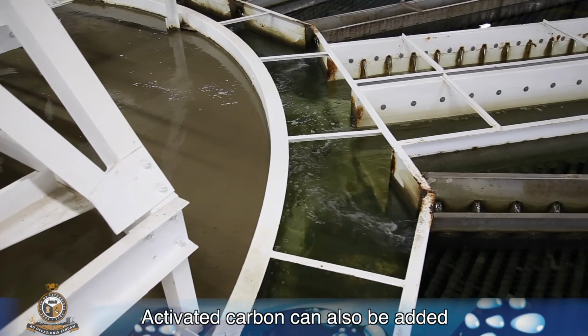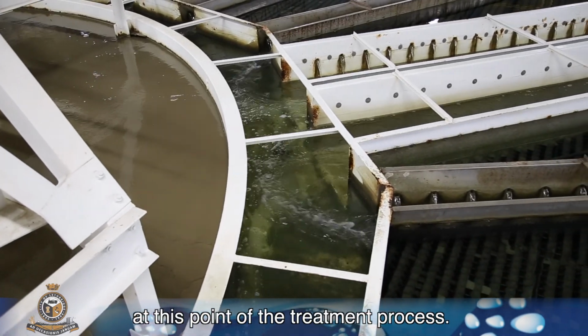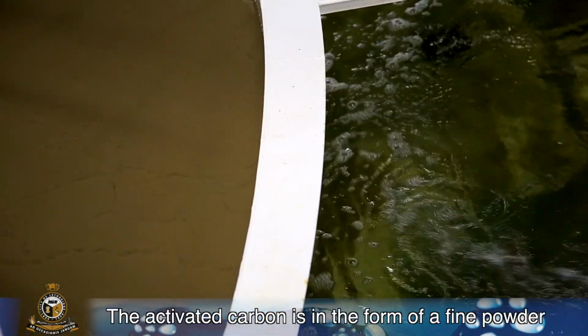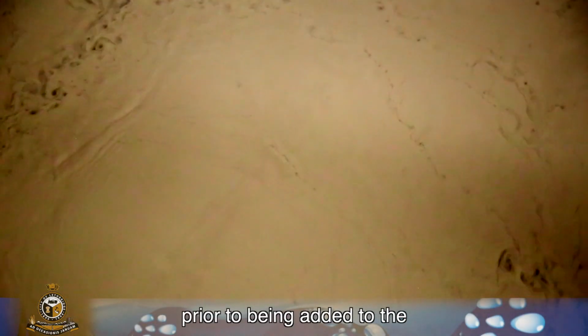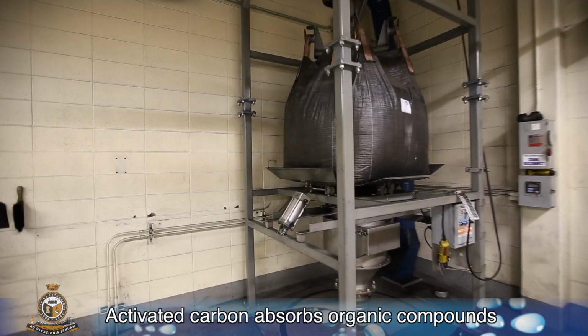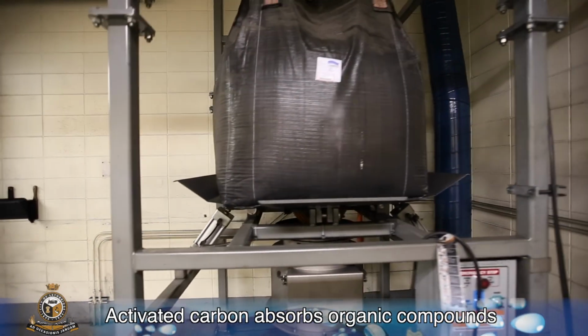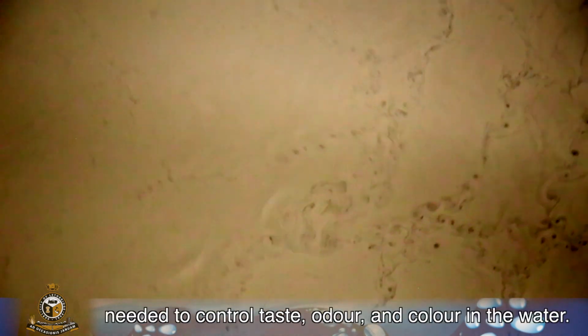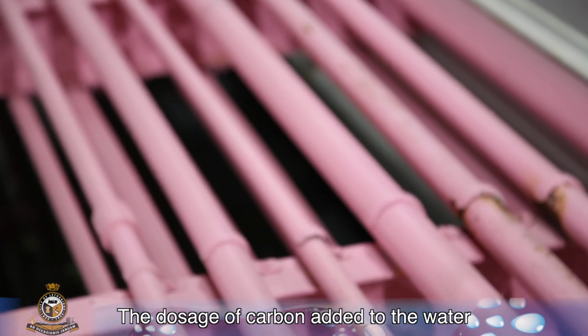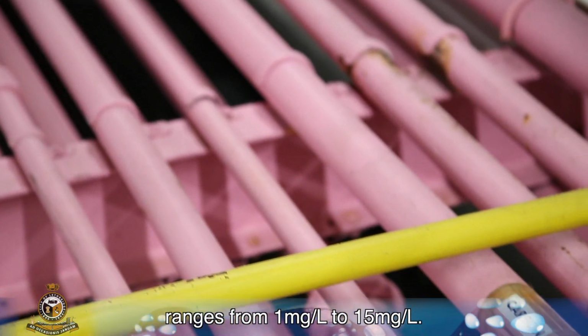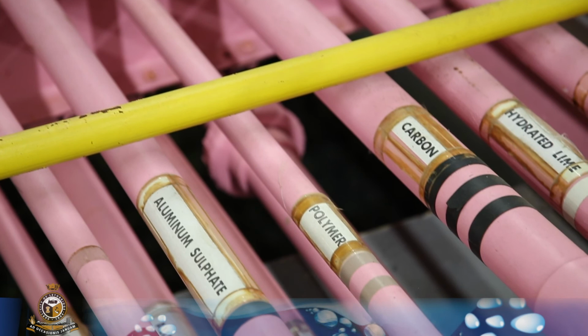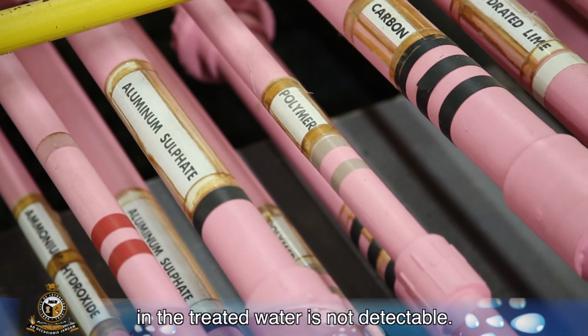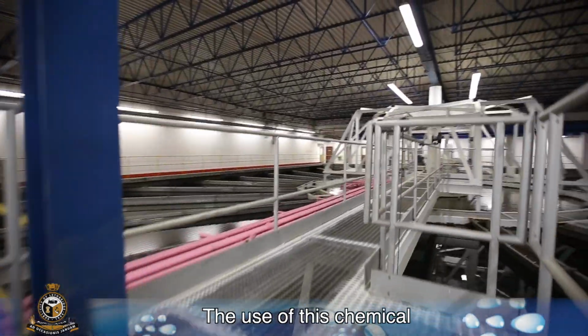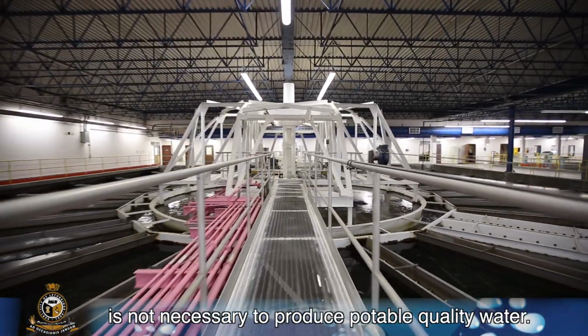Activated carbon can also be added at this point of the treatment process. The activated carbon is in the form of a fine powder that is mixed with water to create a slurry prior to being added to the flocculation zone of the clarifier. Activated carbon absorbs organic compounds found in the water and is used as needed to control taste, odor, and color in the water. The dosage of carbon added to the water ranges from 1 milligram per liter to 15 milligrams per liter. The concentration of carbon remaining in the treated water is not detectable. The use of this chemical is not necessary to produce potable quality water.